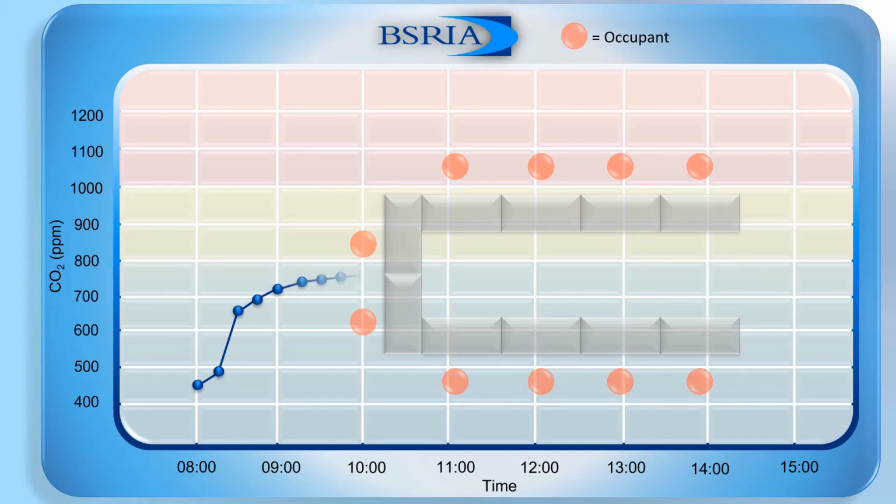When we reach a break, some people leave and there is a decay in some of the CO2 concentration. However, when they return, the CO2 concentration then starts to return to this maximum value of 750 ppm. At lunchtime, there is another break and the majority of the people leave. The CO2 decays significantly then, but when the people return, it does increase. In this case, the ventilation was increased by opening the windows due to the temperature rising in the space.